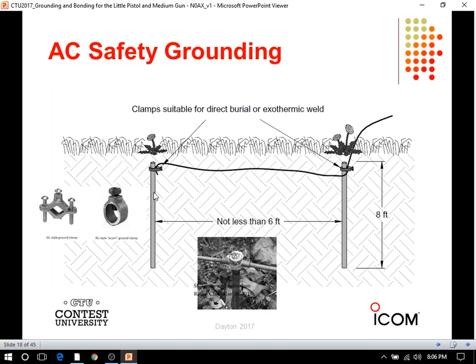This is your piece of number 6 wire, and you use these clamps - no hose clamps, no soldering. Use the real stuff, it's not expensive, it's at the store. This is an Acorn clamp, and this is a GC style ground clamp - if you look carefully, you can see it's got a little hole for you to connect a ground wire to it. These aren't expensive, and you can actually bury them. You run the wire, pound these things down into about 3 inches of the ground, run the wire over there, put the clamps on, and then pound them on down into the ground.